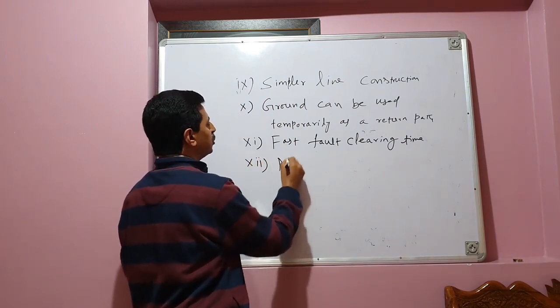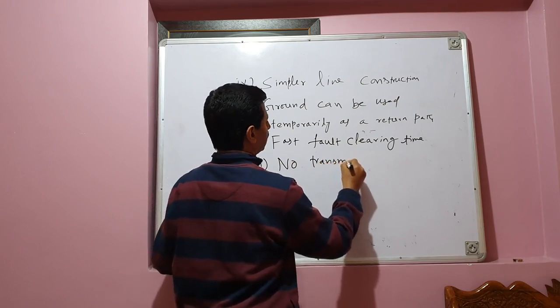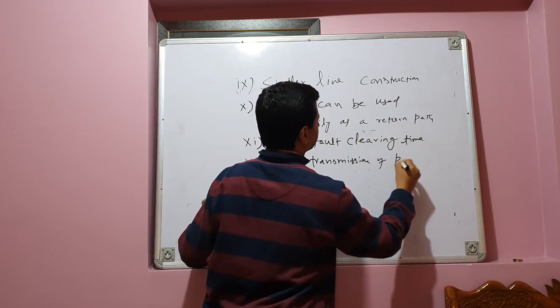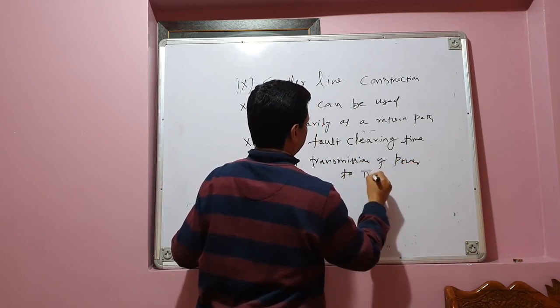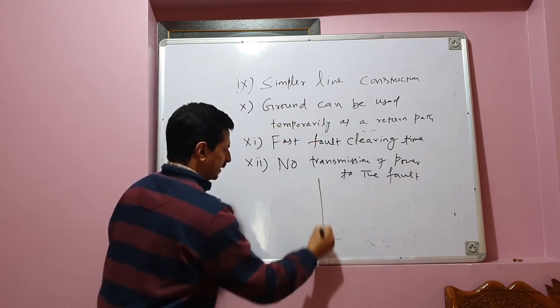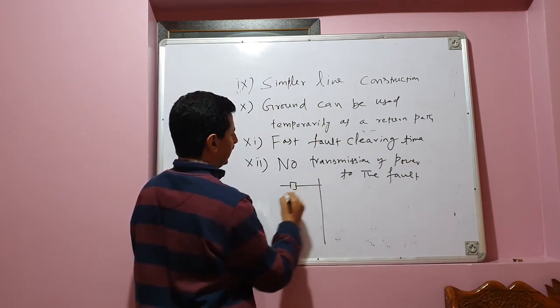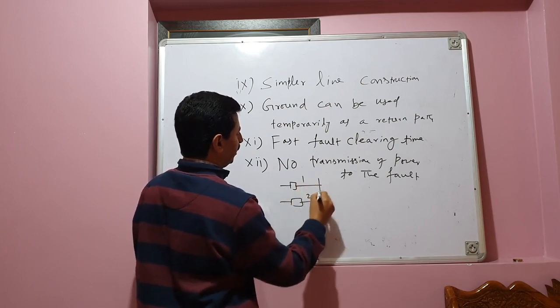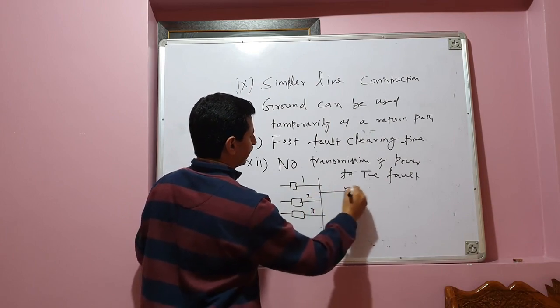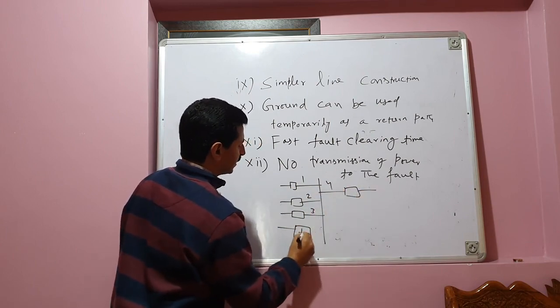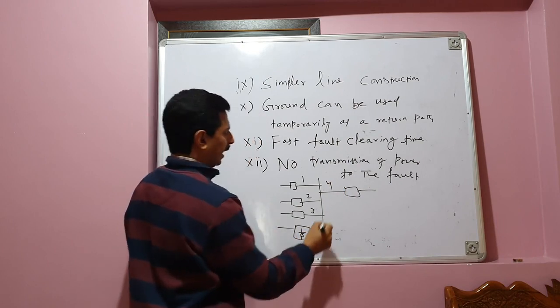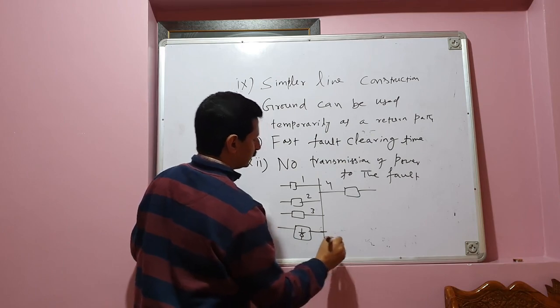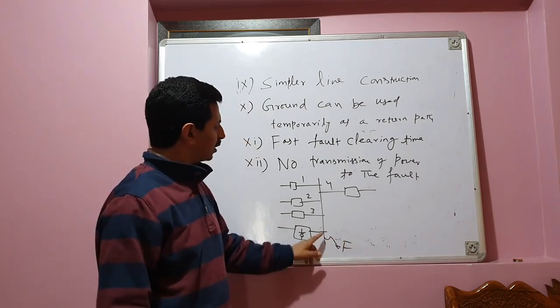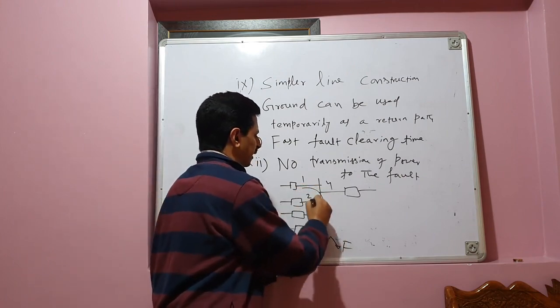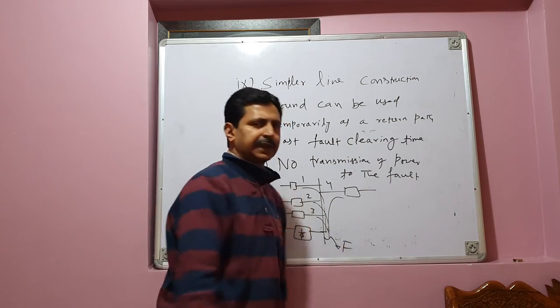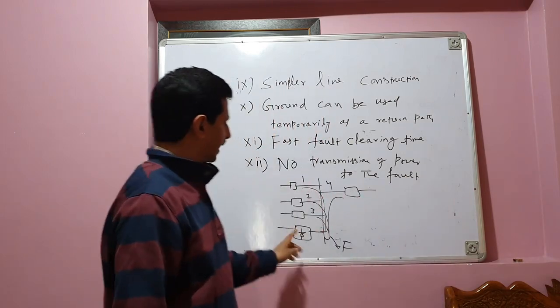Next is no transmission of power to the fault. Let me explain it with the help of a simple diagram. This is a bus, and to this bus various lines are connected. Say these are line number 1, line number 2, line number 3, and on this side we have another line, line number 4, and then we have HVDC transmission, another line which is here. And suppose the fault occurs here. F stands for fault.